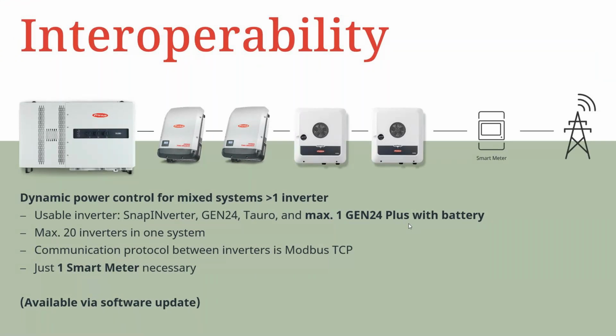It is possible to have dynamic power control of mixed systems with more than one inverter. With just one smart meter as an enabler of this control, you can have multiple devices - it could be a Gen24 Plus, Gen24, Snap inverters, and the Tauro all in one system. All you need is just one smart meter to carry out this control.